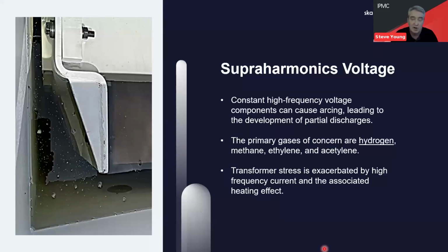So first of all, let's concentrate on the voltage. We know a lot of university-led papers and such like have already acknowledged that the presence of constant high-frequency components can give rise to arcing, particularly on the HV windings of the transformers. Now, as the partial discharges and micro arcs are within the tank, as those arcs are extinguished, there's a bubble that's formed that's predominantly rich, traditionally, in hydrogen, but also in some other dissolved gases, as we call them. You can see the image on the left. There's some tiny little bubbles there. And these systems are often fitted with automated Buchholz relays, which will take the transformer completely out of circuit if that becomes unsafe. Now, wherever we've got high levels of voltage distortion, remember, we're going to start leading into high levels of current drawn at a similar frequency.